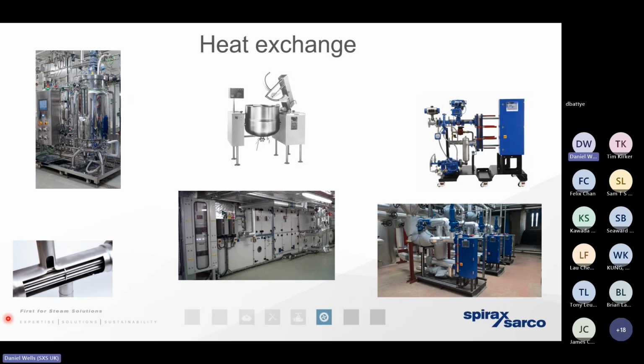There are certain direct processes we can think about. Humidification would be an example. Or if we're using a sparge of steam to heat up a tank of water, that would be an example of a direct process. When we're talking about direct processes, the steam, and most importantly, the condensate, becomes part of that product or atmosphere. In other words, we simply don't have any condensate to return or recover. So for that reason, for the rest of the presentation, I'm really going to focus on those indirect processes where we do need to return the condensate.